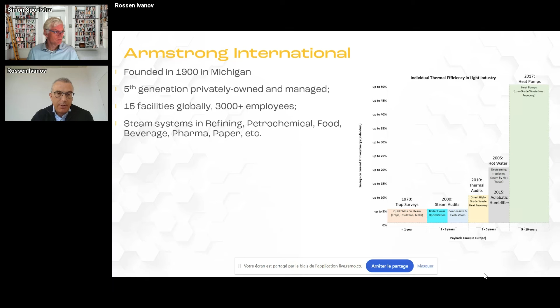Interestingly, our journey has brought us toward energy efficiency, looking at the steam and condensate system, but also recognizing that steam is not the most efficient way to heat below 100 degrees. It's actually a bit challenging to use steam under vacuum, so we went into de-steaming and hot water use as a heating media. And then we crossed the mirror, we went on the other side of the process and found waste heat recovery as a potential for further energy efficiency.